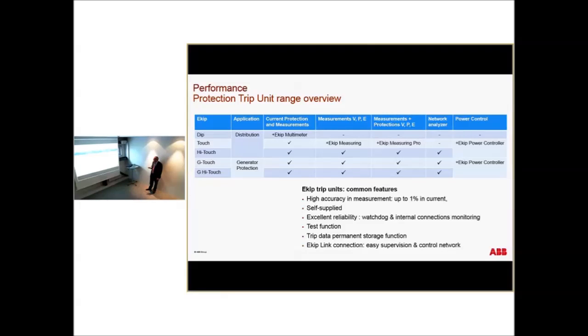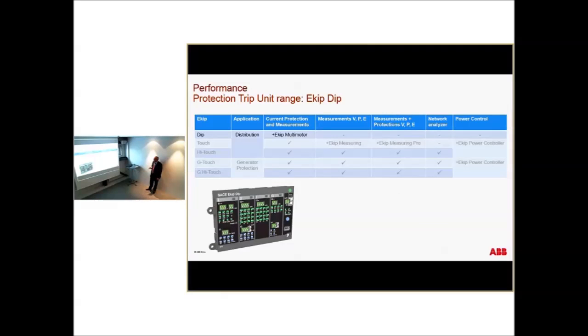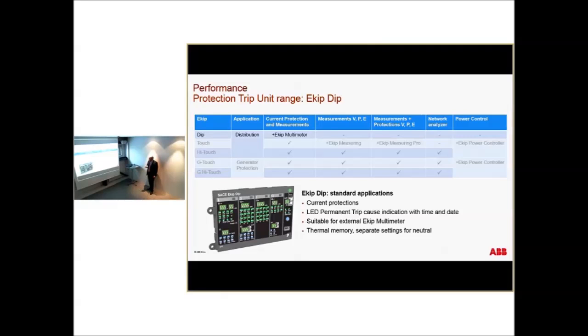You have an Ekip Link connection, easy supervision and control. This is the simplest one. It is used for standard applications, current protection. A good improvement is this nice LED. With the present one, if you're not familiar, the first time you see a red and orange LED, you get worried. The green light gives you more confidence. You say, okay, it works, it's okay. It's a silly thing, but it's an improvement. It's suitable for an external multimeter, an Ekip multimeter. Another improvement is the thermal memory. Now it's also embedded in the basic breaker for protection of motors, cables, and so on. The versions are overload, short circuit, ground fault, and delayed short circuit.